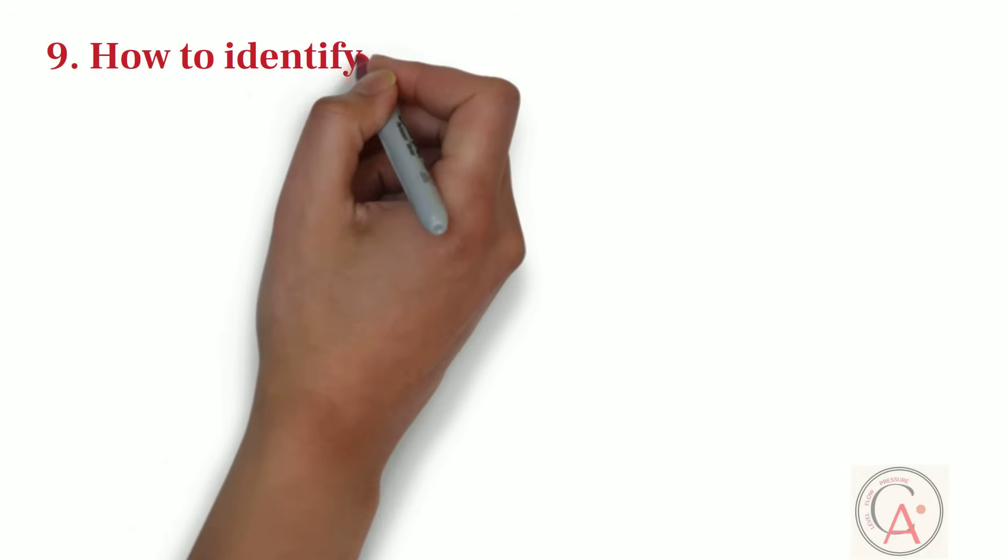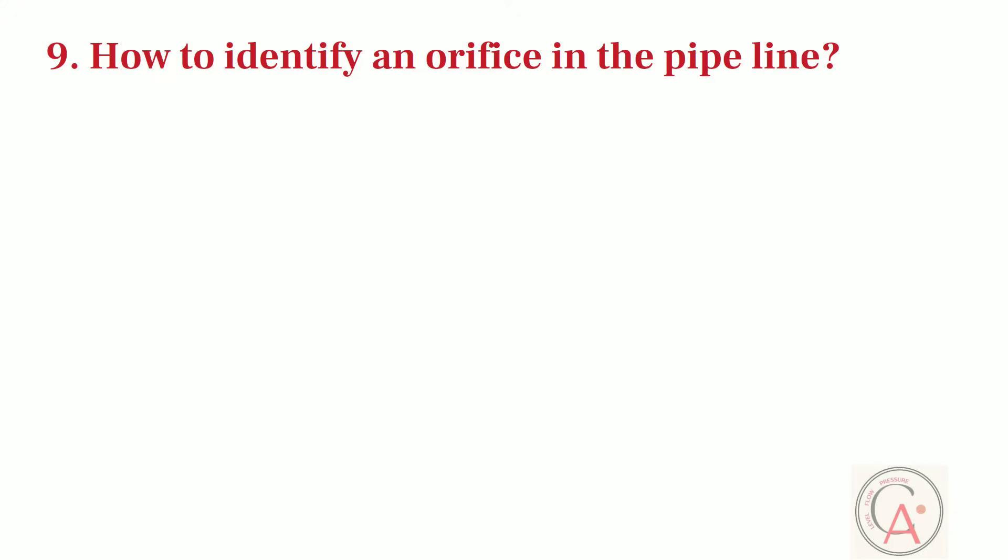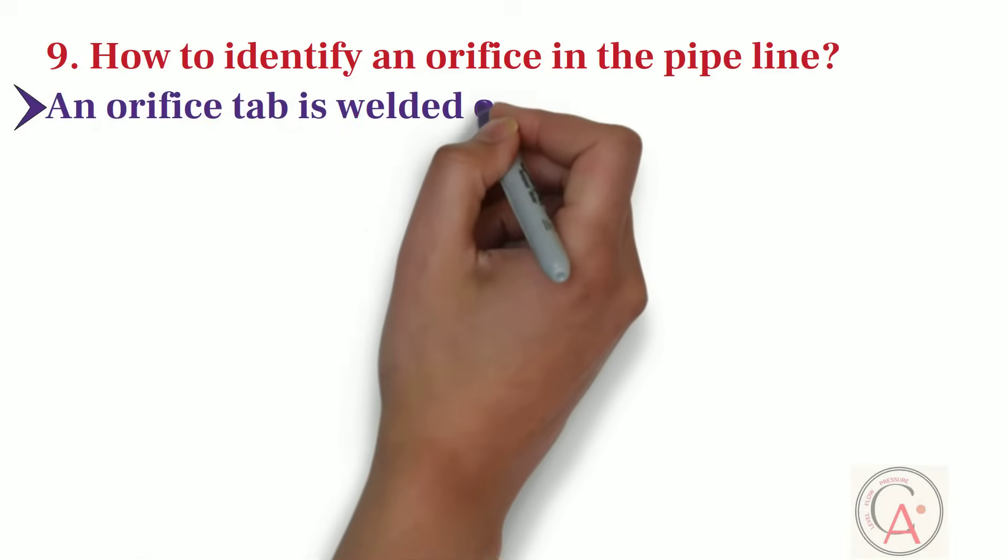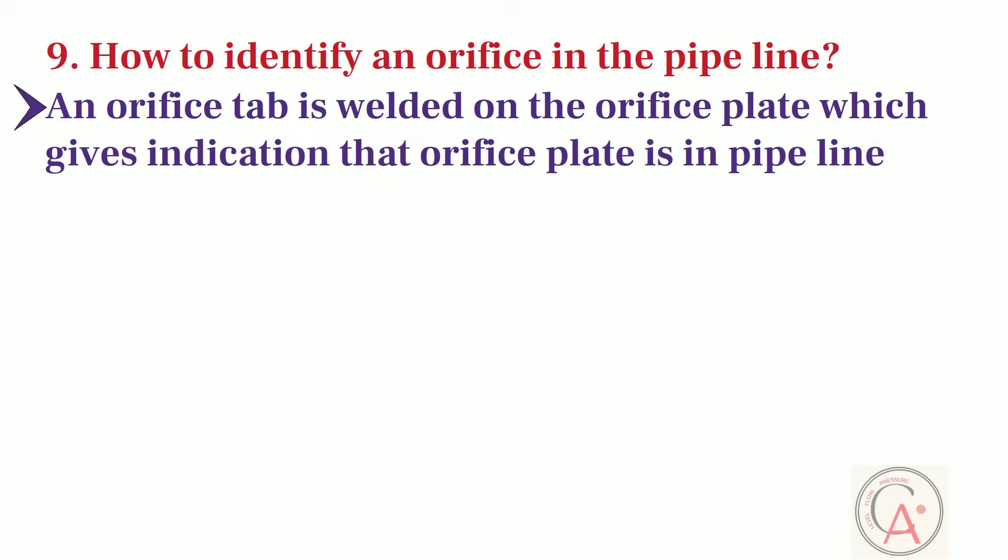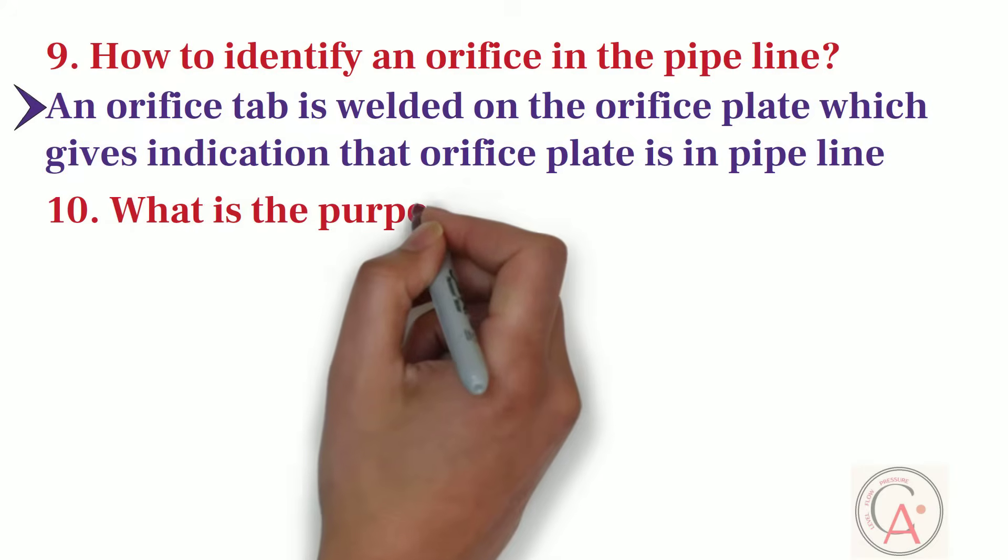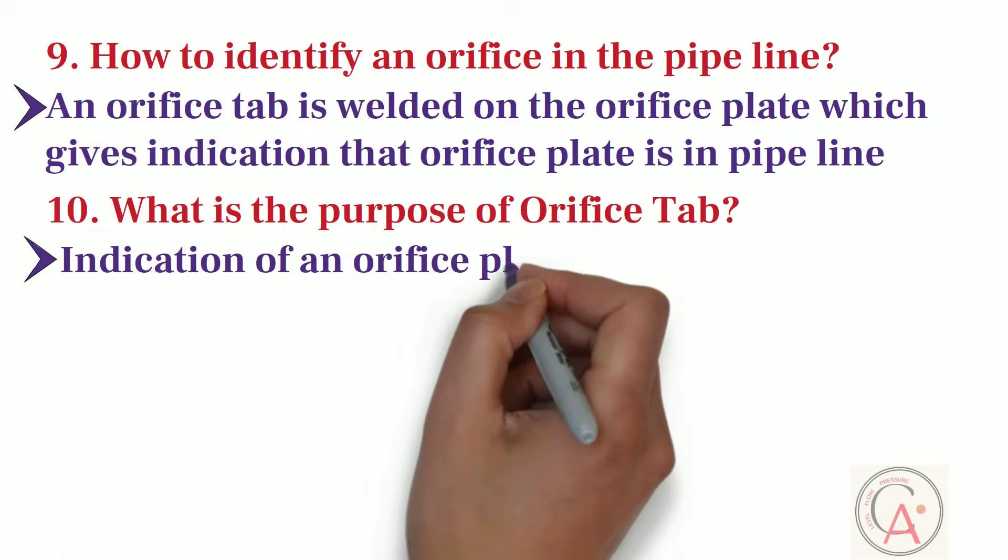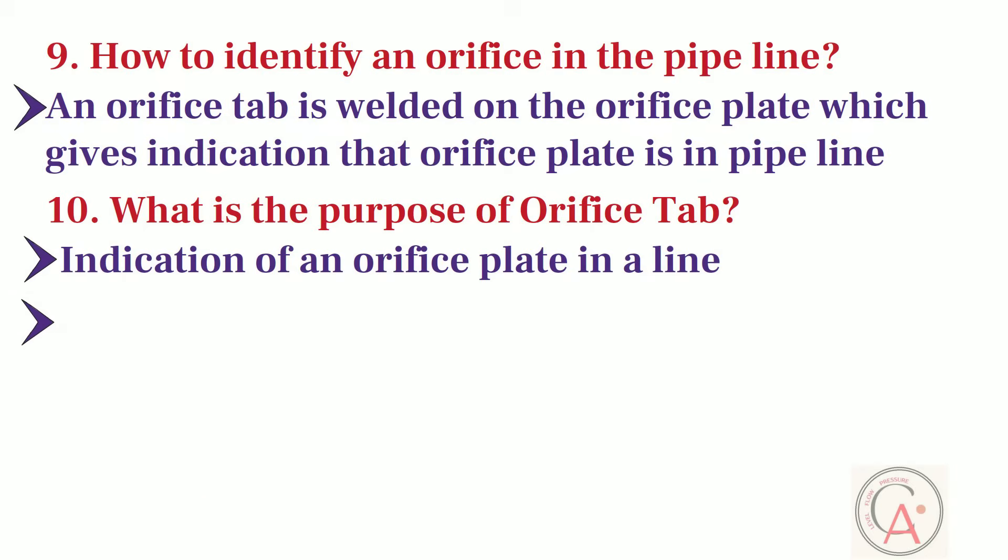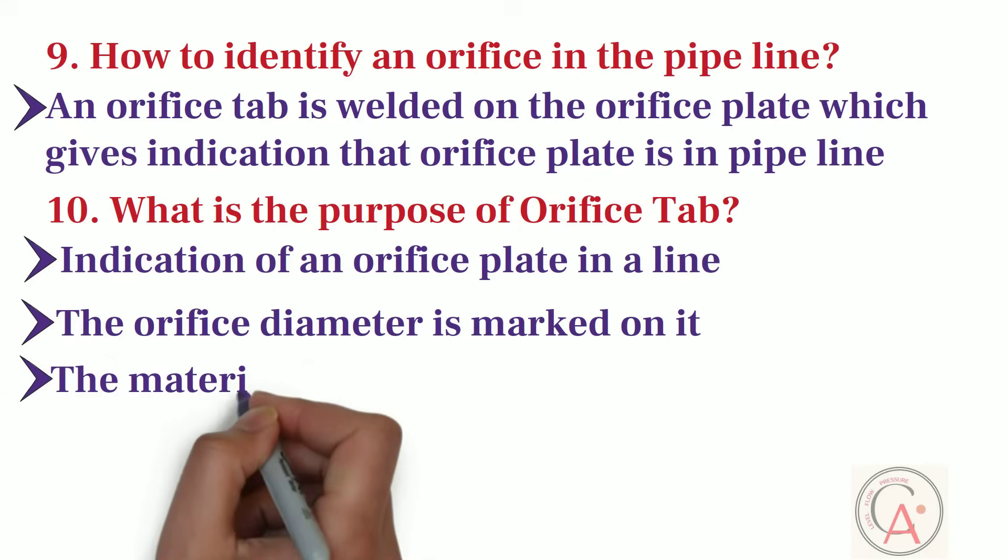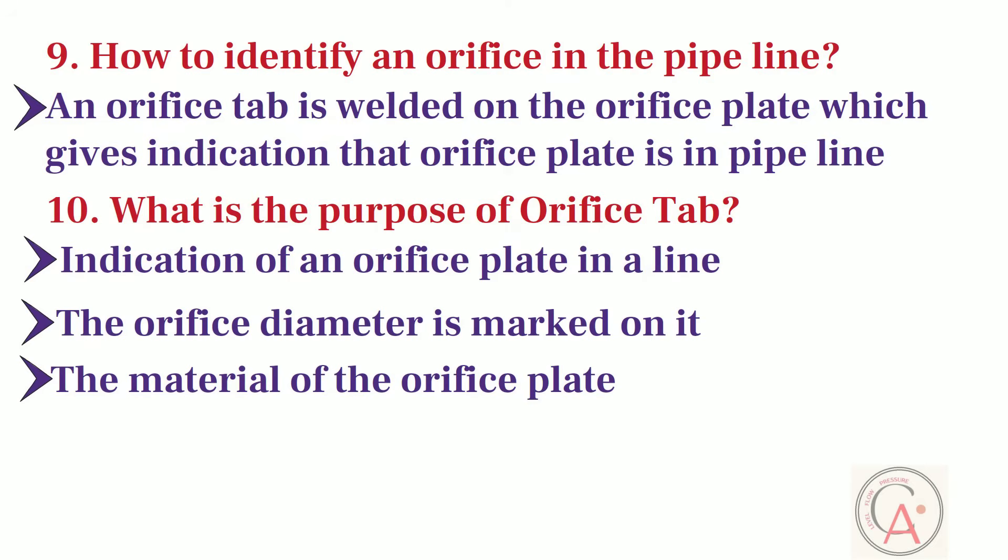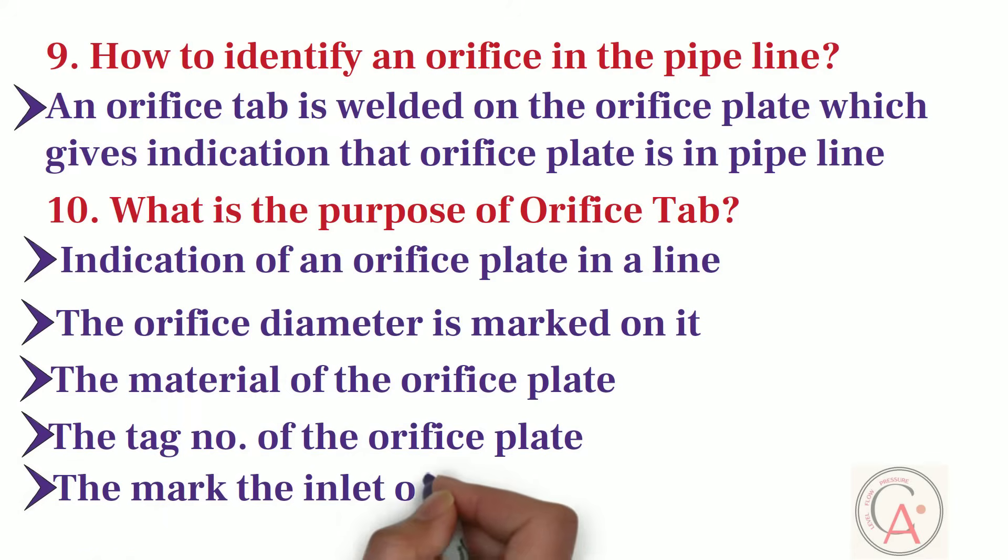Ninth question is, how to identify an orifice in the pipeline? An orifice tab is welded on the orifice plate which extends outer of the line, which gives indication that orifice plate is in the pipeline. Tenth question is, what is the purpose of orifice tab? There are mainly five different applications of orifice tab. First of all, orifice tab gives indication of an orifice plate in a line. Orifice tab is also useful because it has the information about the orifice diameter. In addition to this, it also gives the useful information about the material of orifice plate. Furthermore, the tag number of the orifice plate is also mentioned on it. Last but not least, orifice tab has mark on it, which gives indication of inlet of the orifice.